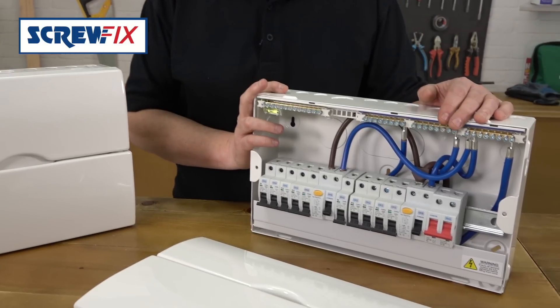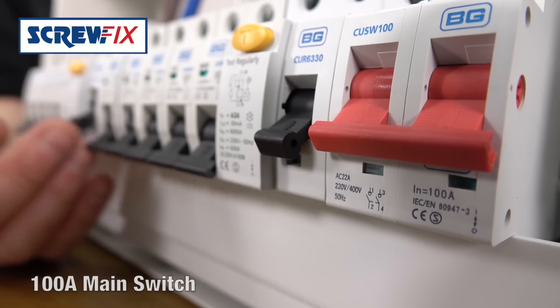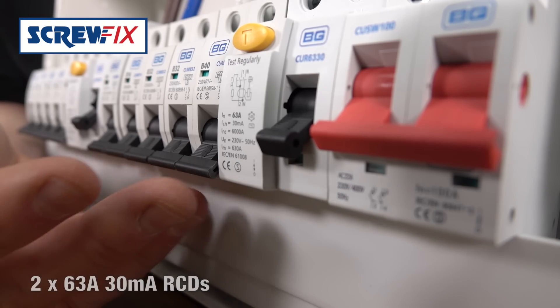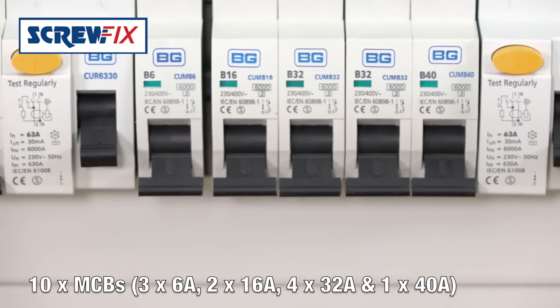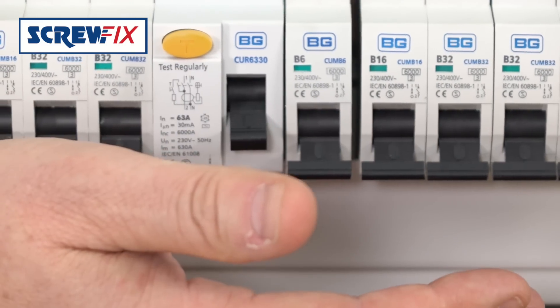The big one here is a 10-way split load board, so you can split circuits onto two separate RCDs. You've got a 100-amp main switch, two 63-amp 30-milliamp RCDs, and 10 MCBs — three 6-amps, two 16s, four 32s, and a 40-amp. Everything you need in a typical domestic installation.